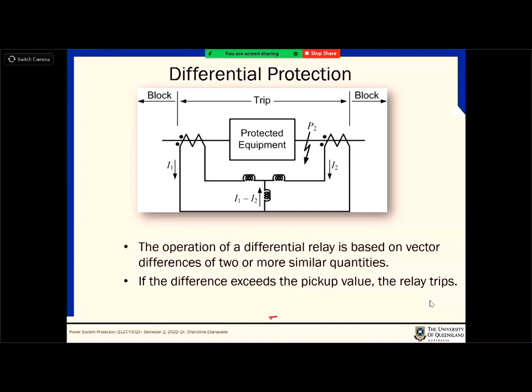Now, the techniques that we described before are not capable of identifying that sort of small currents, because sometimes they are basically comparable to load currents. So there's no way to identify it. So for these devices, when we want to look at these sort of small currents, let's say a generator or transformer or some sort of protected equipment, what we do is simply measure input current and output current.